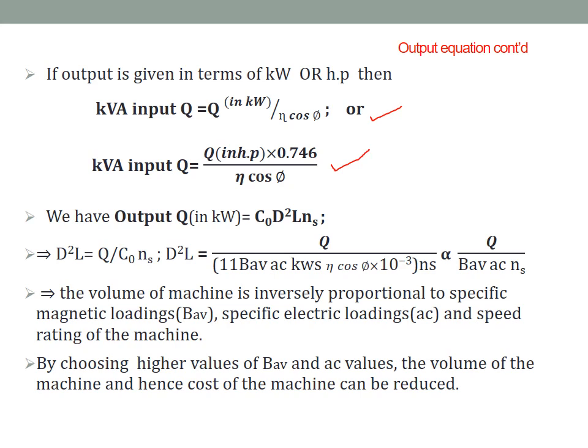D²L is proportional to Q / (B_avg × AC × Ns), as the other factors are constants. The volume D²L of the machine is inversely proportional to specific magnetic loading, specific electric loading, and the speed rating of the machine. If you choose higher values of B_avg, the volume of the machine can be reduced. Similarly, if you choose a high value of AC, the volume, size, and cost can be reduced. If you go for a higher speed rating machine, the size will become small, provided there is no restriction on speed.